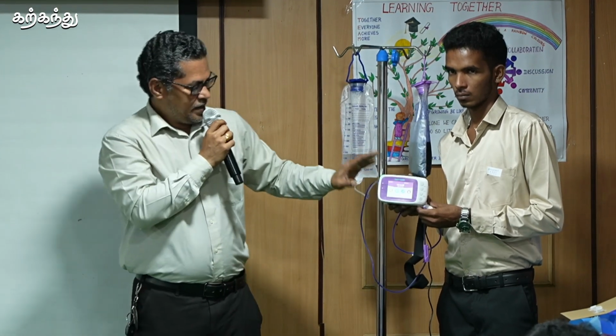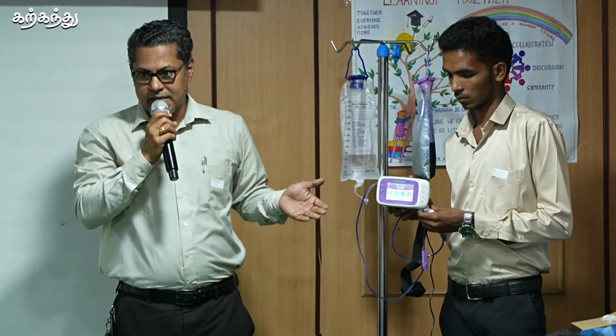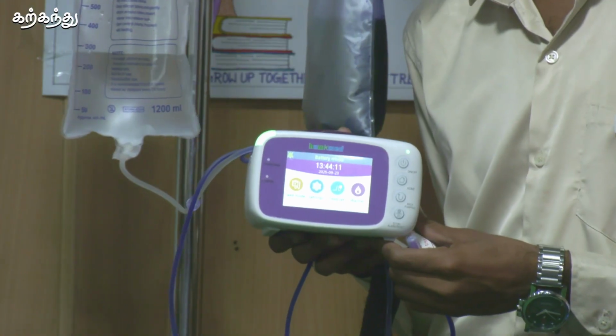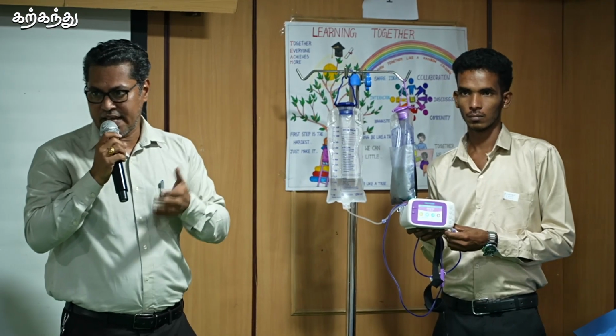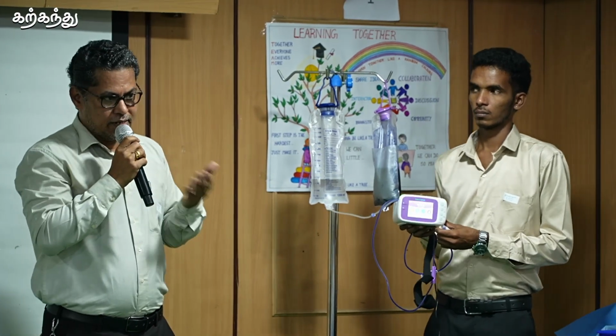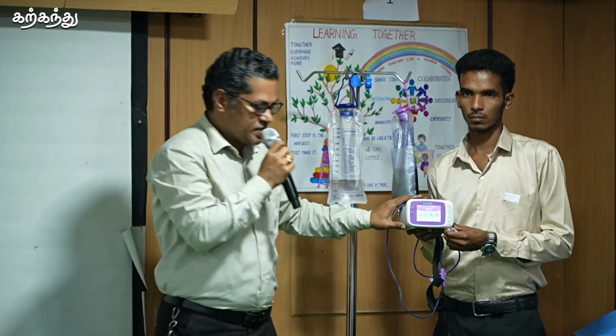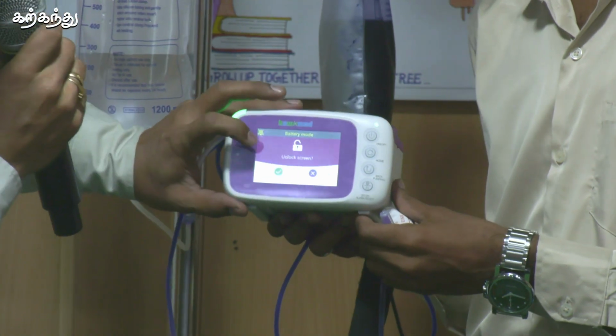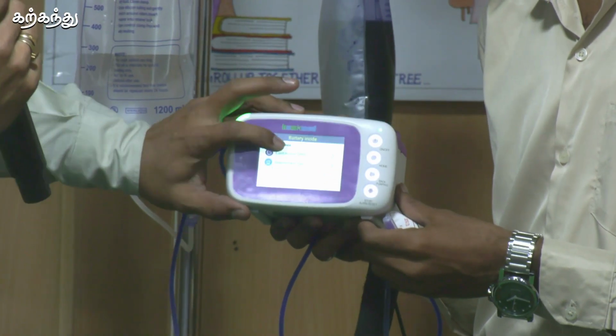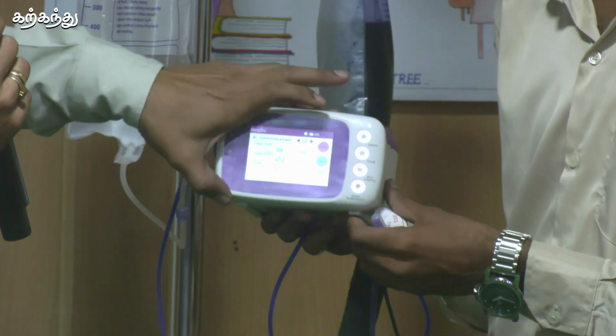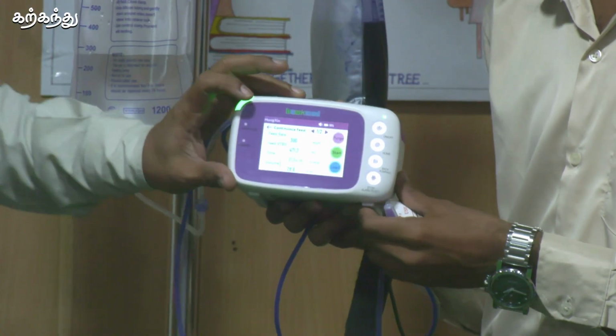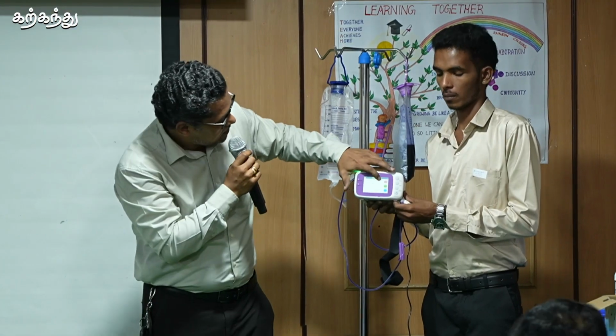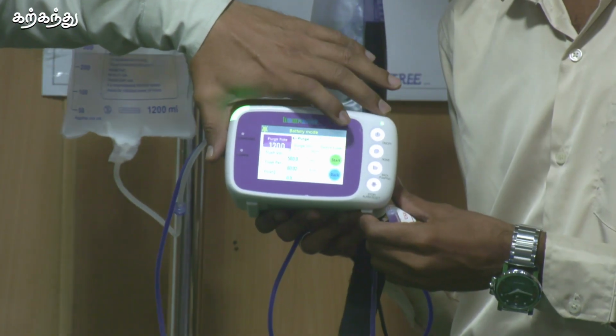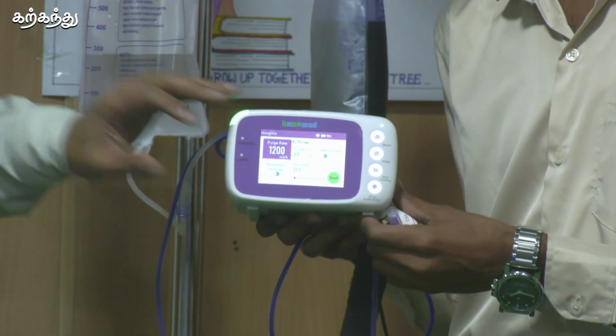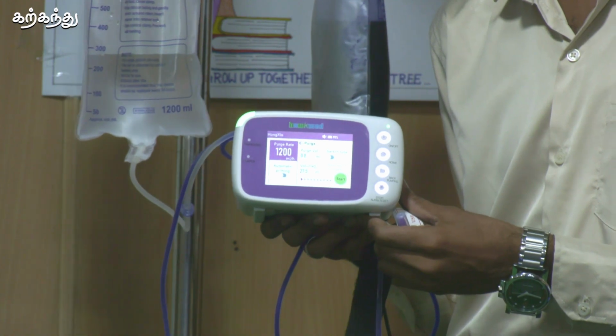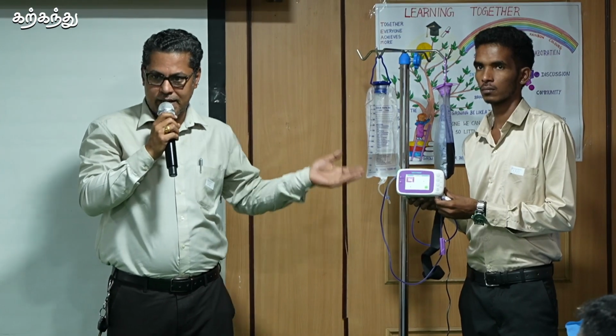At the same time, just as we do priming for IV devices and administration sets, here it is called purging. Once we set the feed rate as well as the flush rate, we can start the purging, where automatically the priming will start. If you want to do manual priming, that can also be done.